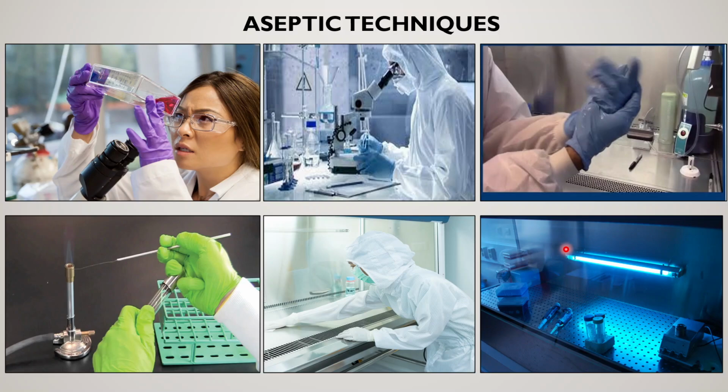Before each use, the UV light is kept on for about 15 minutes, and at the beginning of the day, when we are starting our work, we keep the UV on for 30 minutes. After that, before you start working inside the cell culture hood, you will switch off the UV, because UV light is harmful to our skin. It might cause cancer.